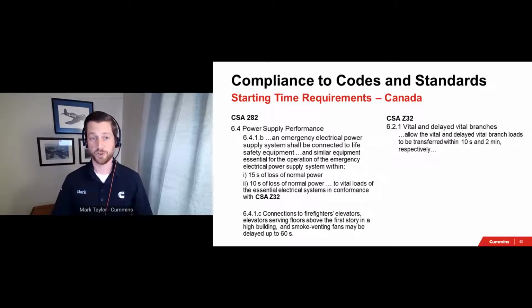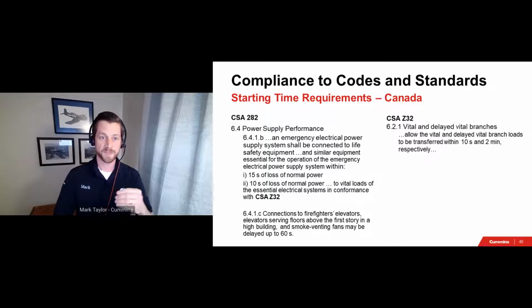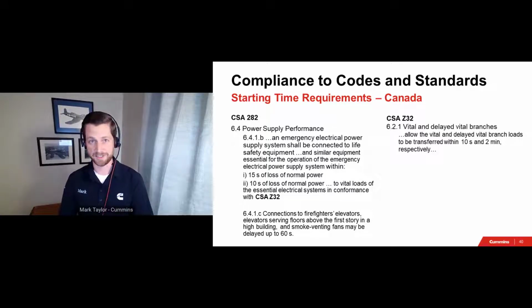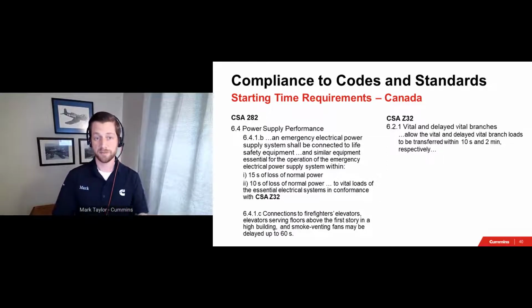Once again, I'd like to take a quick aside for our Canadian audience members. The counterparts to NFPA 110 are CSA 282 and CSA Z32, like I mentioned earlier, and it adds further requirements for healthcare applications. One key distinction of CSA 282 is that for life safety equipment, 15 seconds is the time requirement for acceptable power to be provided on the load side of the transfer switch or power supply system. A 10-second requirement, however, does come into play for vital loads of essential electrical systems for healthcare per Z32.